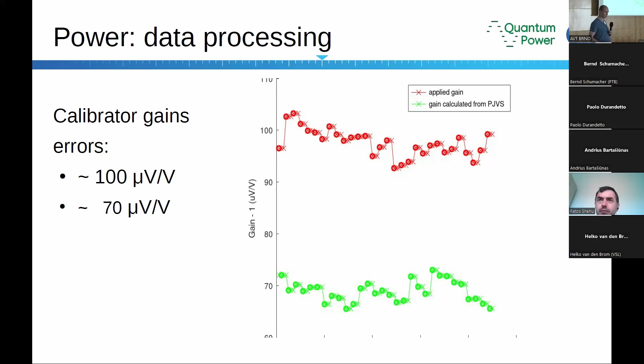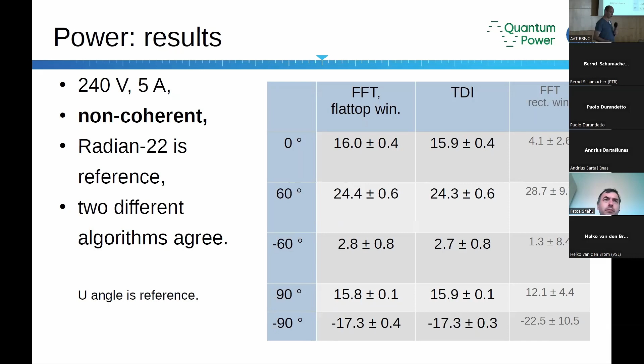So again, this is a non-coherent measurement. And we got about 16 or 25, 24 ppm is the worst case error. It is not the best, but we still have to think that this is a non-coherent measurement, and I have spent zero time calibrating the digitizer itself. Everything was automatic. When the Radian device and the transducers come back from Norway, I will finish the measurements for the coherent setup, and I expect much smaller uncertainties.